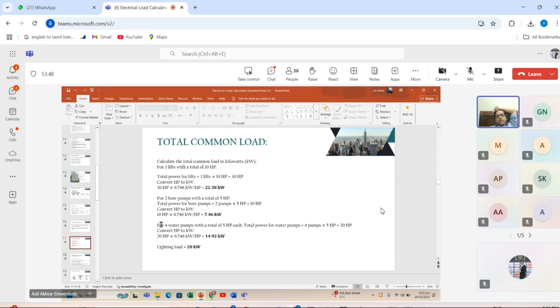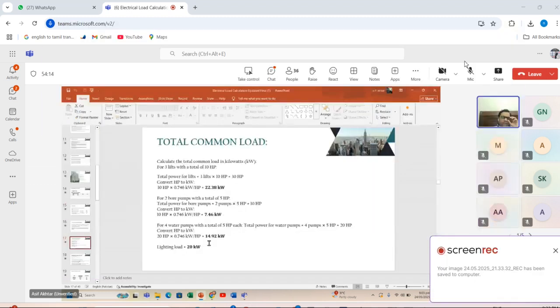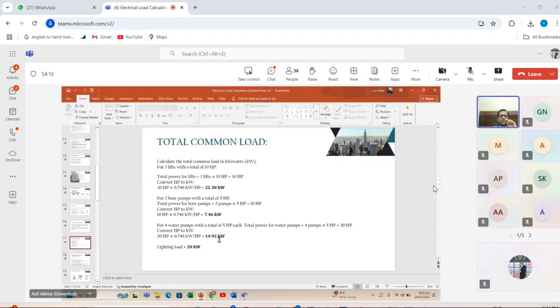Is that right? And now for 4 water pumps with a total of 5 HP each. So total power for the water pumps is 4 pumps multiplied by 5 HP, which is equal to 20 HP. Now convert HP to kilowatt. As I told you, 1 HP is 746 watts, and you have to convert watts into kilowatts, so you divide 746 by 1000, which is equal to 0.746. And you know that the lighting load is 20 kilowatt. Now all the common load calculations have been done.